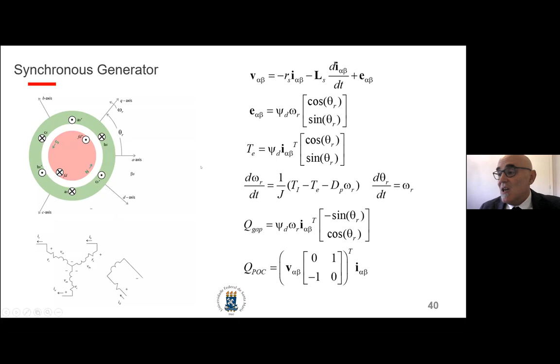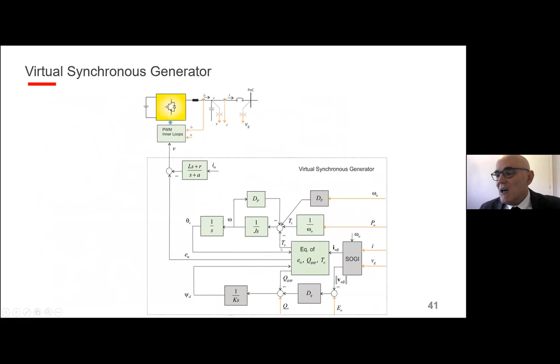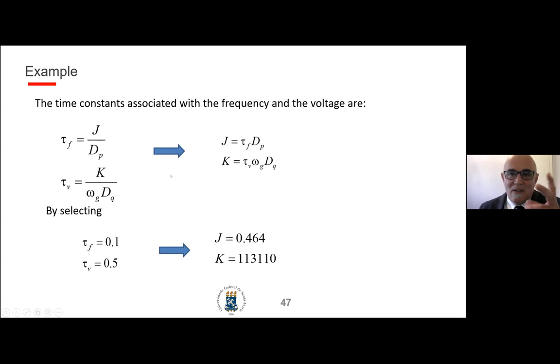We implement these dynamic equations in C code, and the inverter emulates a synchronous machine. We have the swing equation and some damping coefficients associated with the droop, so dP and dQ relate to the droop. One difference here is that you can somehow decouple steady-state and transient performance, whereas with droop, changing the droop coefficient changes both the transient and the steady state. In this synchronous machine implementation, it's possible to keep those two characteristics decoupled.